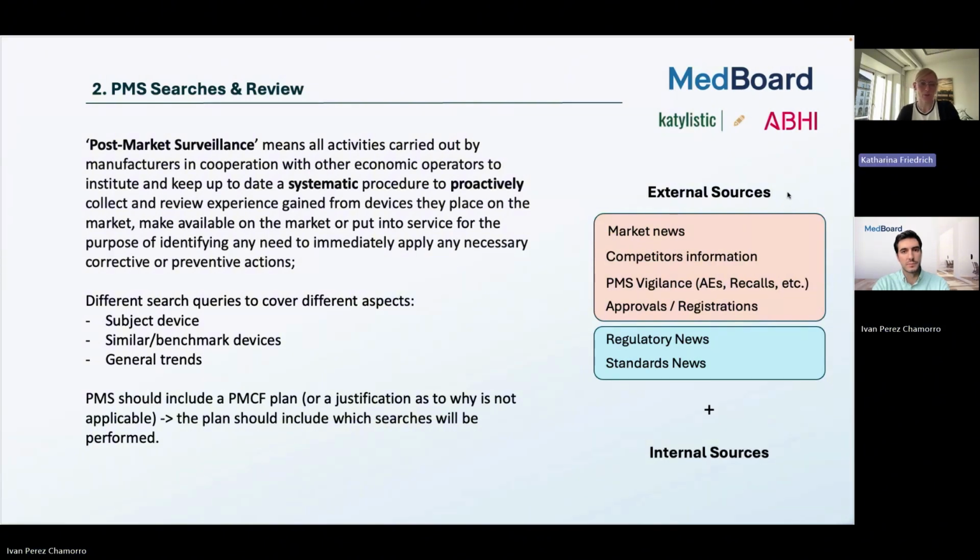Yeah, I mean, of course, post-market surveillance covers a lot of activities. So everything that you perform as a manufacturer as soon as the device is on the market refers to post-market surveillance. But as you just mentioned, I think in this webinar, we want to focus a bit on everything that we collect from external data sources, like literature search databases, but of course also vigilance databases.